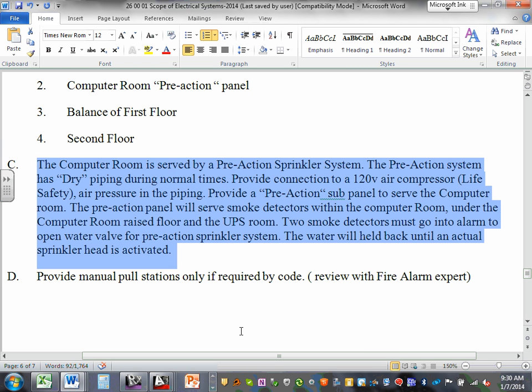So if somebody's walking with a ladder and knocks a head off, it just lets air out - it won't release water. You still need the smoke detector to confirm it's a fire before water comes.